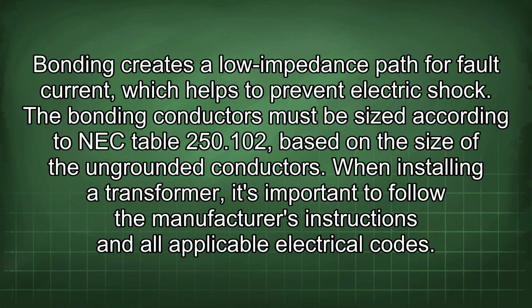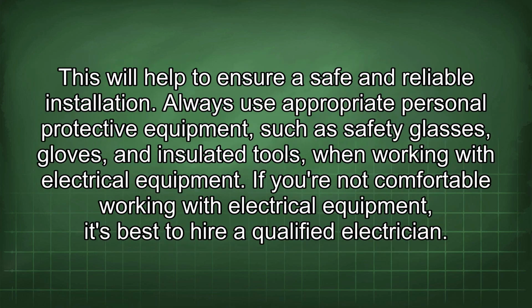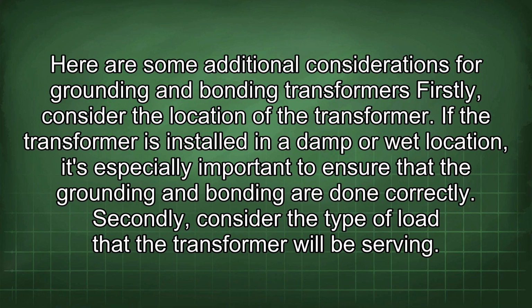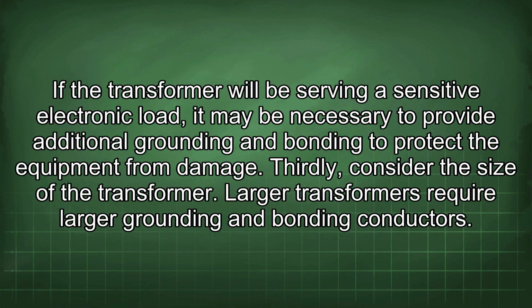When installing a transformer, it's important to follow the manufacturer's instructions and all applicable electrical codes. This will help to ensure a safe and reliable installation. Always use appropriate personal protective equipment, such as safety glasses, gloves, and insulated tools, when working with electrical equipment. If you are not comfortable working with electrical equipment, it's best to hire a qualified electrician. Here are some additional considerations for grounding and bonding transformers. Firstly, consider the location of the transformer. If the transformer is installed in a damp or wet location, it's especially important to ensure that the grounding and bonding are done correctly. Secondly, consider the type of load that the transformer will be serving. If the transformer will be serving a sensitive electronic load, it may be necessary to provide additional grounding and bonding to protect the equipment from damage.